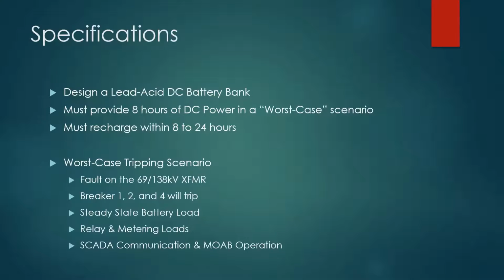Some specifications for the battery bank are that it has to be a lead-acid battery. The battery must also be able to provide 8 hours of power in a worst-case scenario and be able to recharge within 8 to 24 hours. This worst-case scenario is a fault on the transformer, which would cause breakers 1, 2, and 4 to trip, which would need power to be able to trip.